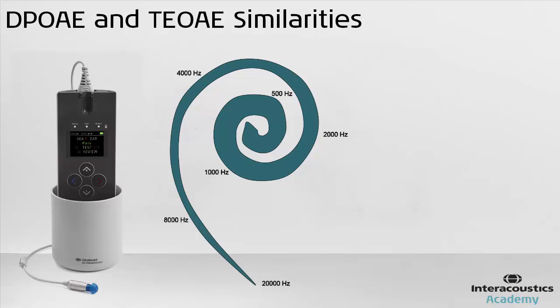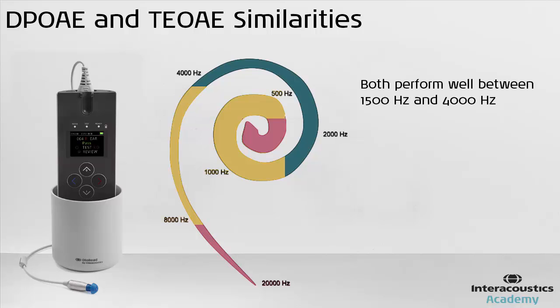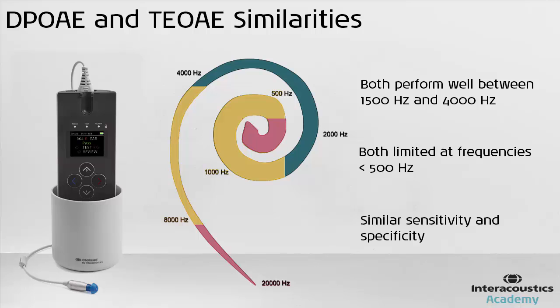There are many other similarities between TEOAE and DPOAE. Firstly, they both perform well between 1500Hz and 4000Hz. Secondly, they are both limited at testing frequencies of 500Hz and below. Lastly, the sensitivity and specificity of DPOAE and TEOAE are considered similar and are for most people not a reason for preferring one over the other.